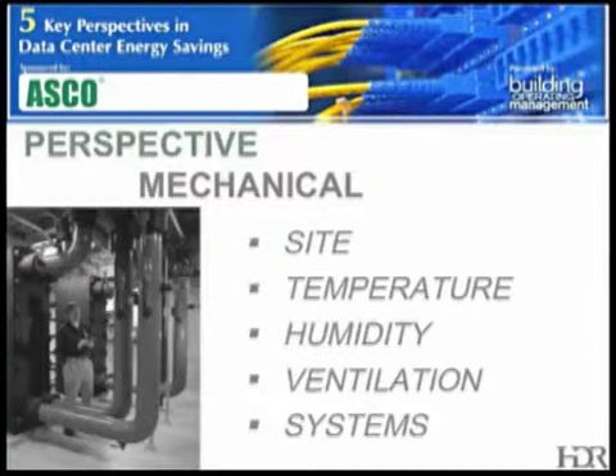They require substantially more first costs. They're going to require a lot more maintenance. They will provide much better energy performance if you're in a climate zone where you have extended periods of mechanical cooling required. We found through our designs that typically larger machines in the range of 1,200 to 1,500 tons per unit are usually optimal.